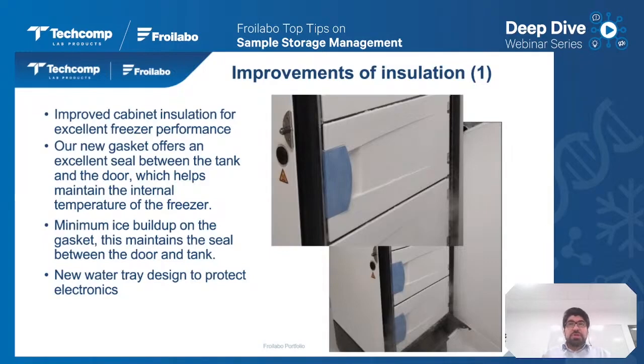Also, in terms of a power shutdown, as much as we can insulate the chamber, if a power shutdown happens in the building or something happens, we can contain the cold inside the chamber and keep the samples safe for longer hours. Another thing we improved was the injection foam, which we do in the factory. We increased the density of that by 15%, which has a huge contribution to performance. That means you will lose less heat from the chamber and have less refrigeration usage.